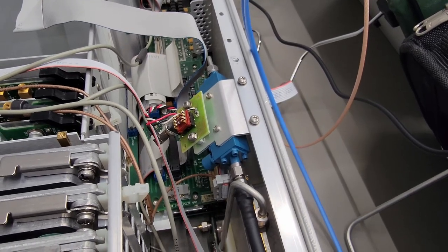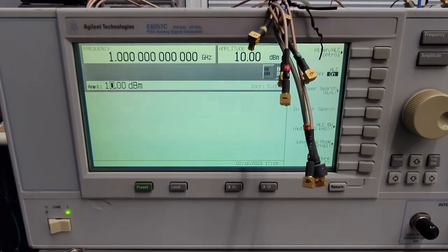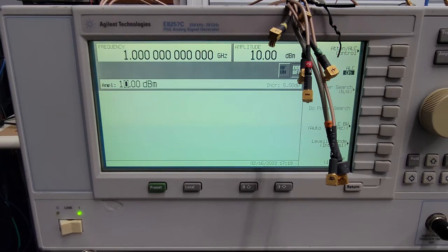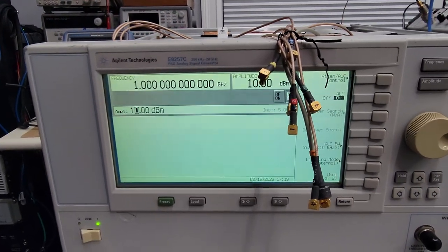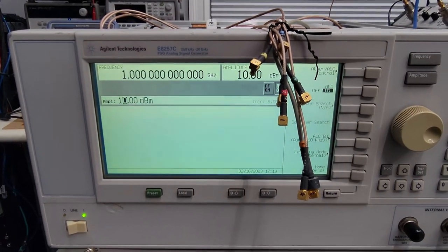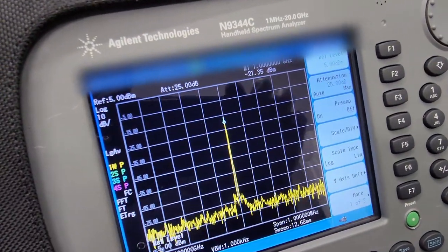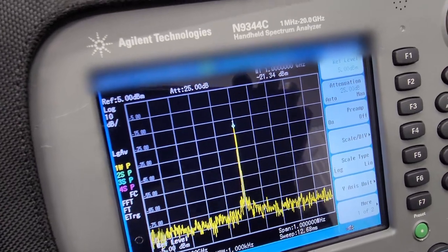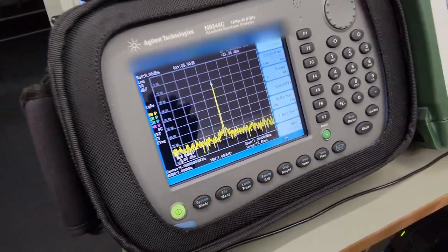And as you can see right now, I've got the instrument set to 1 gigahertz and 10 dBm CW, no modulation. And 10 dBm is high enough that the attenuator is switched completely to the through path, so there's no attenuation. And if we come over here and look at our output on the spectrum analyzer, indeed it is still minus 20 dBm low.